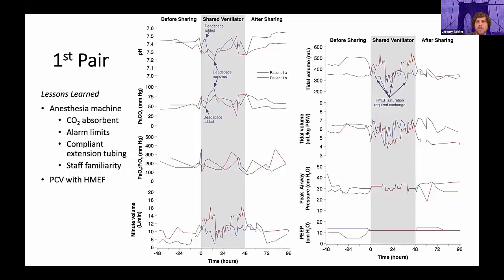Liquid was building up in the ventilator circuit so quickly. So now the HME filter was failing, not only because you had exhaled moisture from the patient, but you had the CO2 absorbent converting CO2 to water, and then that water sitting on the other side of the filter. There were other important limitations, especially around alarm limits and the physical configuration of the anesthesia machine. Collectively, that prompted us to never use an anesthesia machine again for the purposes of ventilator sharing.